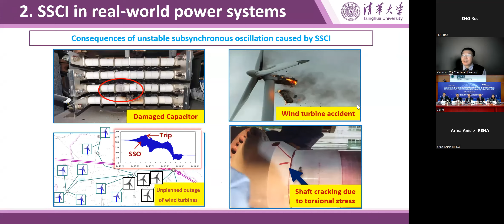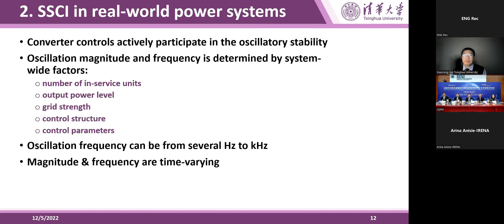A lot of research has been done in this area, showing that converter control actively participates in the SSCI. The magnitude and frequency of the oscillation is determined by system-wide factors, including the number of in-service units, output power level, grid strength, control structure, and control parameters. What's more, the magnitude and frequency are time-varying around the events.